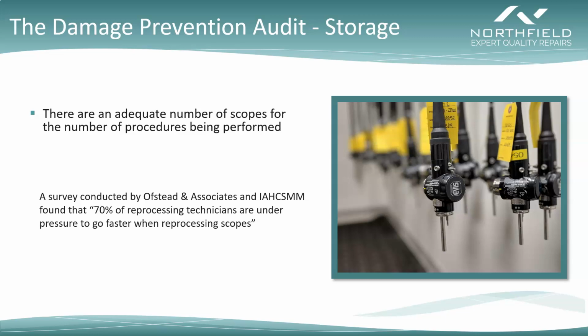Now, keep in mind that properly reprocessing a scope has about 130 steps. And generally speaking, human performance metrics indicate that if a process is really well understood and well trained, you're going to make a mistake about 1 out of every 100 opportunities. However, if you add stress into that mix, that incidence of mistakes goes up from 1 in 100 to 1 in 10. So that means that generally speaking, if there's no pressure on a technician, they might make one mistake in the entire 130 steps of reprocessing.